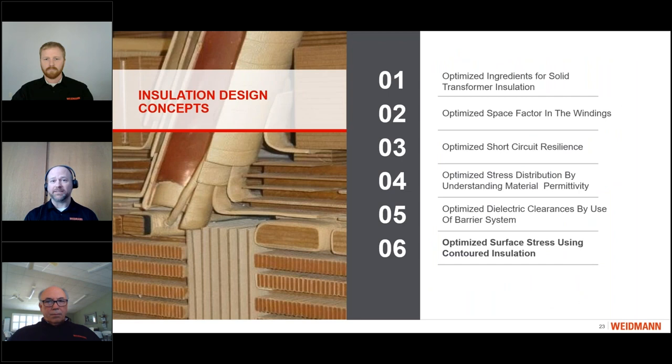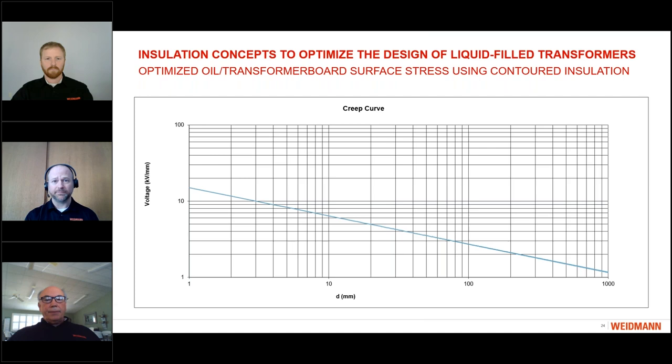So the second topic I'll talk about for optimizing your insulation design is optimizing the surface stress by use of contoured insulation. Similar to the Weidmann reference curves for oil gaps, there is a Weidmann reference curve for what's called an oil transformer board surface stress. We also colloquially refer to it as a creep curve because the stress, when you see a failure path, it can creep along the surface.